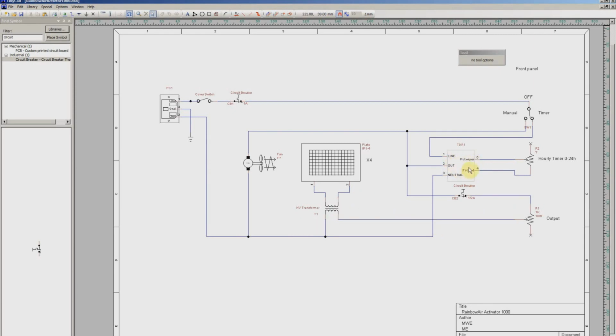So when this times out, and it's simply a resistor capacitor network. This is the variable resistor, and there's a capacitor inside of here, an RC timer. When this times out, relay drops out, and the voltage stops coming out the output. Pretty straightforward. Now the other thing we have over here is on the neutral side. You have this bus that goes down here and picks up the neutral side of the fan, the neutral side of the transformer, and gives the timer module a neutral reference to ground.